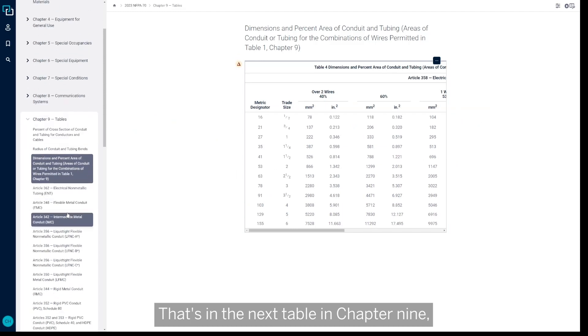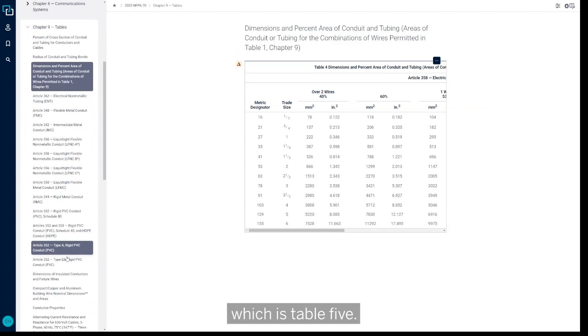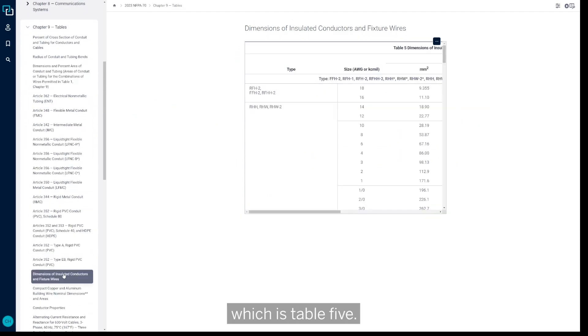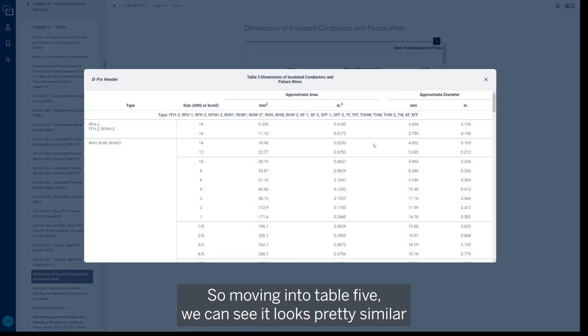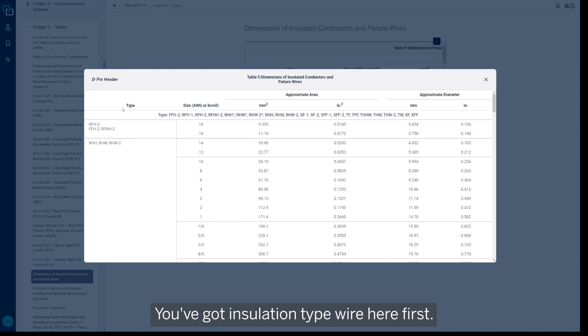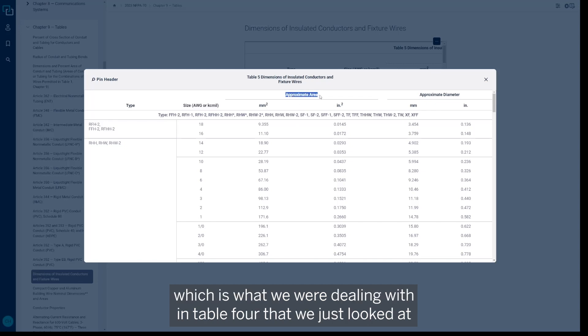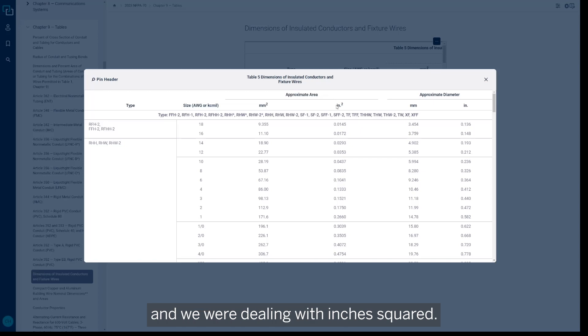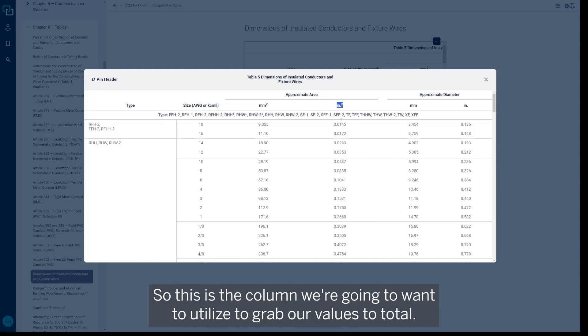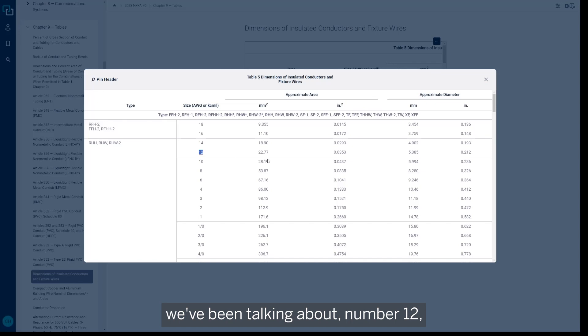So where do we get the individual area in inches squared for each individual conductor? That's in the next table in Chapter 9, which is Table 5. So moving into Table 5, we can see it looks pretty similar to some of the other tables we've looked at. You've got insulation type wire here first. We've got wire size, and then we go into approximate area, which is what we were dealing with in Table 4 that we just looked at, and we were dealing with inches squared. So this is the column we're going to want to utilize to grab our values to total.